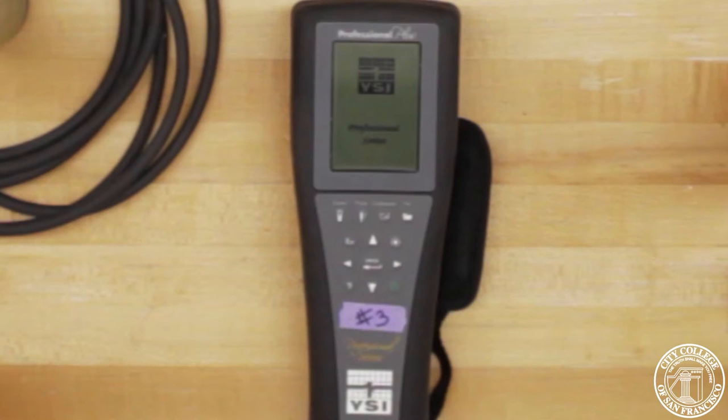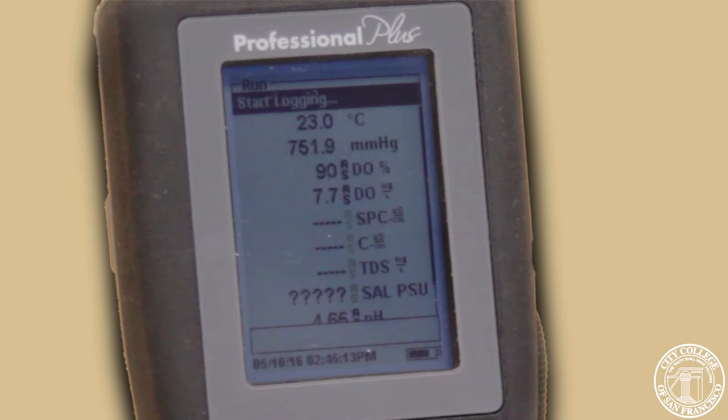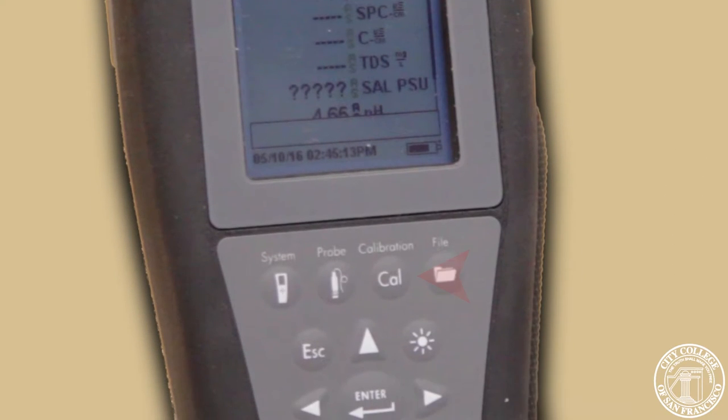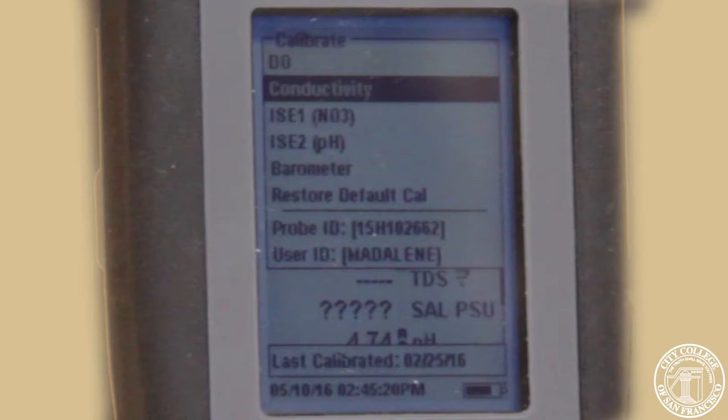Next, we're going to turn on our meter. Our meter is going to show the run screen. We want to calibrate instead. We're going to go down and select ISE2 (pH). That's where our port is at.